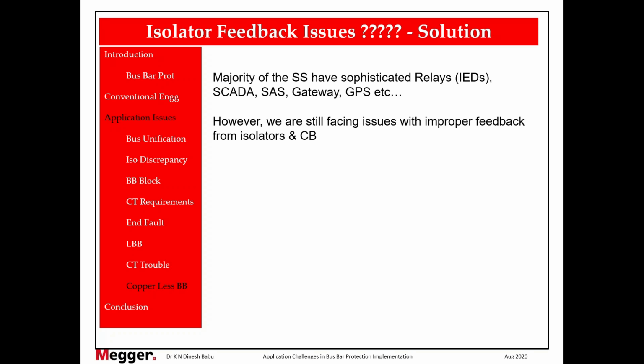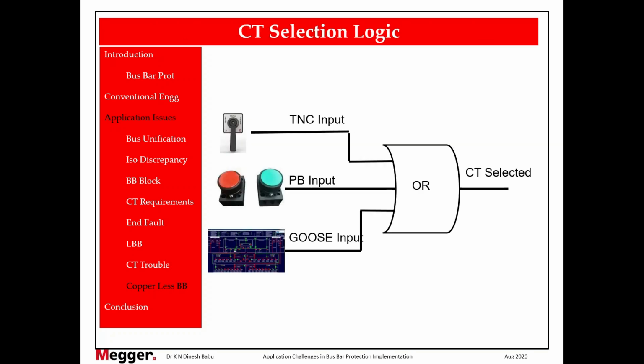But sometimes a lot of wiring is to be done to get the signals from the isolator. And moreover, by aging and weather conditions, the isolator mechanism boxes are not working properly, and we are not getting proper signal to the control room. So we have implemented an alternate arrangement in our system. Instead of getting the isolator wiring, we used a replica of the isolator. If isolator 1 is closed, then push button 1 is closed, and if isolator 2 is closed, then push button 2 is closed.